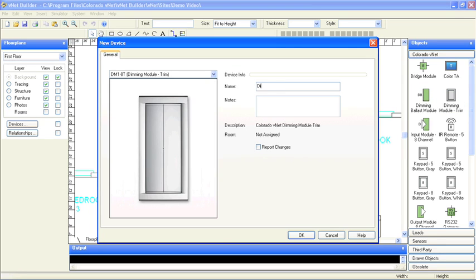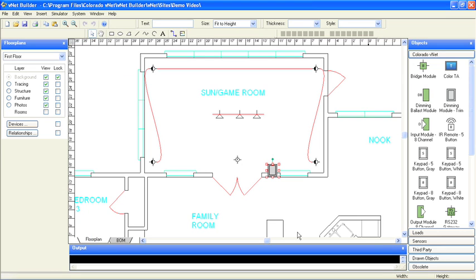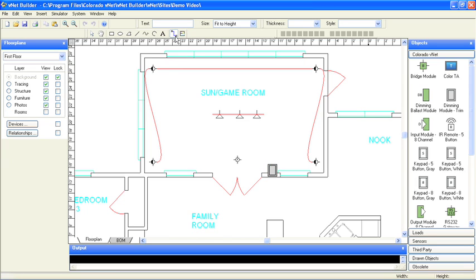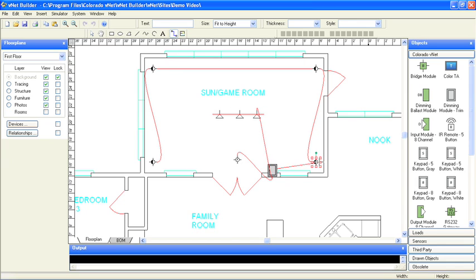Each dimming module is designed to work off one 20-amp circuit from a breaker, which is then turned into eight 240-watt circuits, which can be used individually or ganged together to get up to a 1920-watt dimmable load. The same Relationship tool that defined the circuits will make the connections between the dimmer legs and the load circuits. Notice that since the dimmer is installed near the load legs, the Romex runs can be quite short, saving both material and labor costs over the traditional home run method.